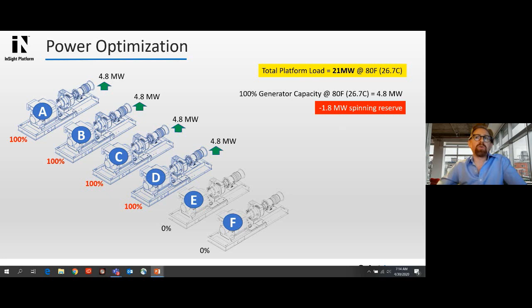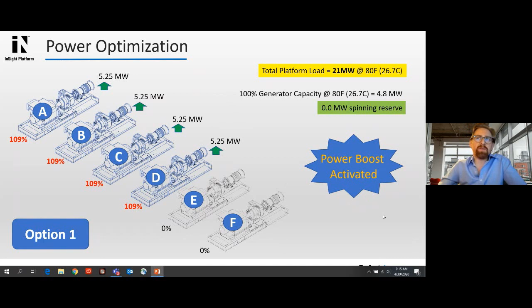So option 1, customers that have equipment health management would be able to activate what we call power boost. In this instance, we can get upwards of 10% additional power out of an operational engine. So in this case, we could run these engines up to 109% of the rated capacity, and they would be able to generate 5.25 megawatts apiece. In which case, we'd be able to meet the 21 megawatt load, and we would basically deplete any spinning reserve capacity. Now, this would buy the operations some time to start up units E or F to reestablish a healthier spinning reserve capacity. But this would prevent the entire platform from going dark. So option 1 would be the activation of power boost.